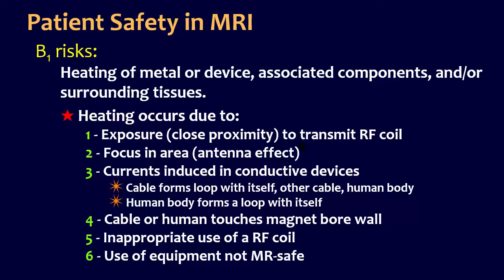I also keep hoping there'll be more research. I'll see more research at this meeting in these areas that will help us figure out how we can be safer in our use of magnets with our patients. There's focus in an area, which some people call an antenna effect. There are currents that can be induced in conductive devices, as shown very nicely in Dr. Kugel's talk previously.